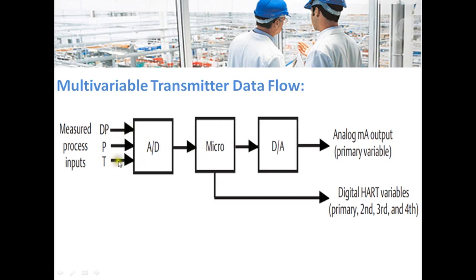Fieldbus devices also support multivariable data flow. Take a DP transmitter, which measures differential pressure, temperature, and static pressure — with 4-20mA, only one variable (the primary variable, i.e., DP pressure) can be transmitted. Whereas with fieldbus, all variables can be transmitted at a time. This is also applicable to a Coriolis flowmeter, which measures multiple physical variables like density, temperature, and mass flow rate — all of which can be transmitted simultaneously using fieldbus.